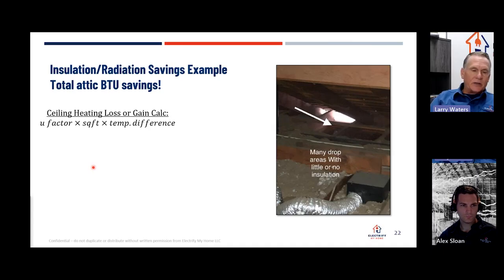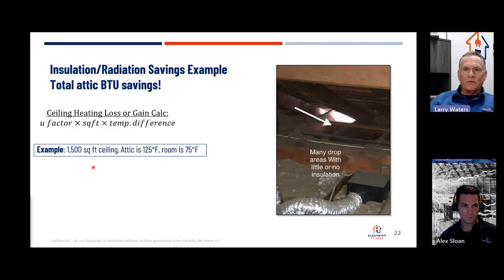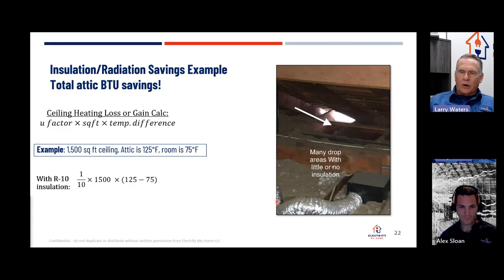So what we're looking at is the ceiling heat gain. If we have our same 1,500 square foot house, the attic is 125, and we're cooling the room to 75, which gives us a 50-degree temperature differential. Just do the math there. If we have R10 insulation, and R10 insulation is really, if you can see the rafters, and it's not good and there are gaps everywhere, I use R10 as that benchmark. If we've got cellulose that's perfectly installed all the way up to the top of the rafters, it might be a little bit more, but you can figure that on the U factor.